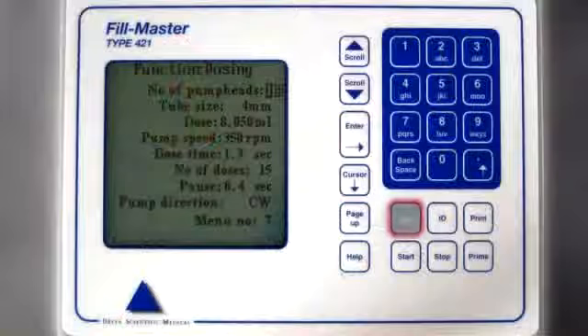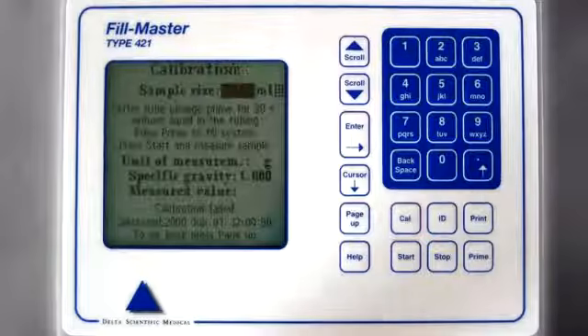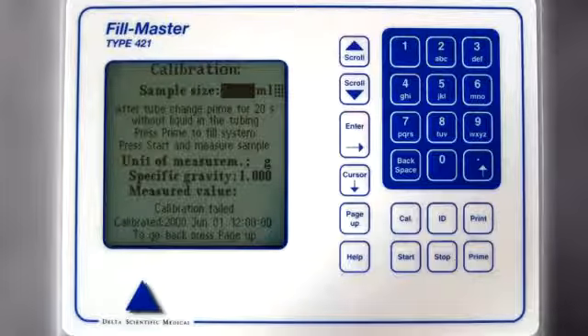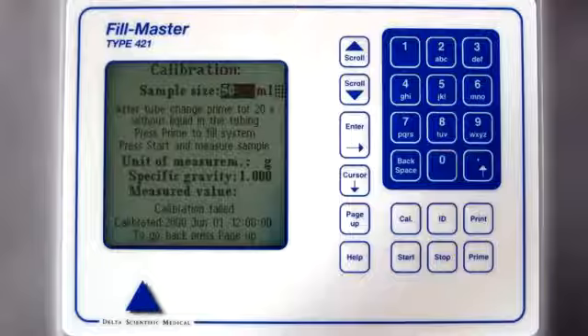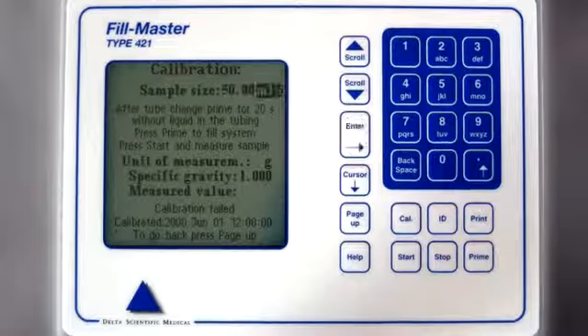When you have completed a setup, you may press the Calibration button in order to get the calibration window. The cursor will be in the sample size field. Here you may key in the volume of the sample you want for calibration. You may choose any volume that will give you a good reading on your measuring cylinder or balance. Often you would choose a volume 2 to 10 times higher than the dose size you have asked for. Higher values give better accuracy. Press Enter to confirm your choice.